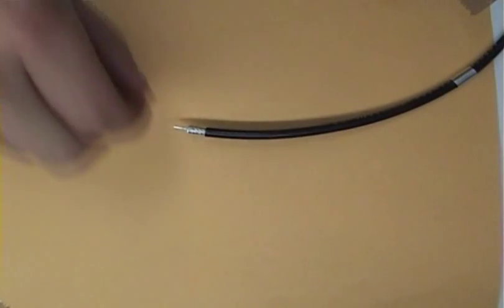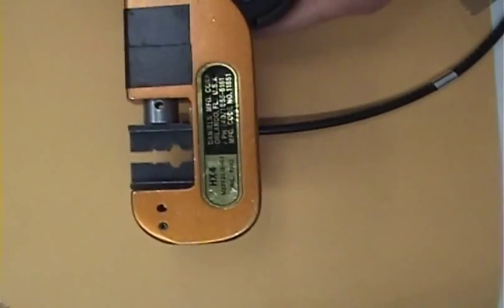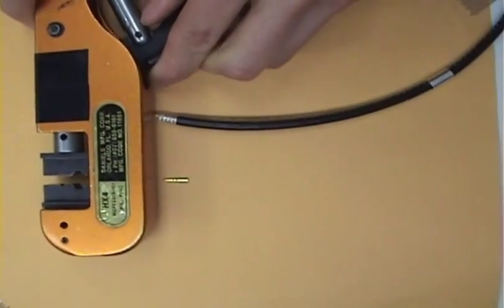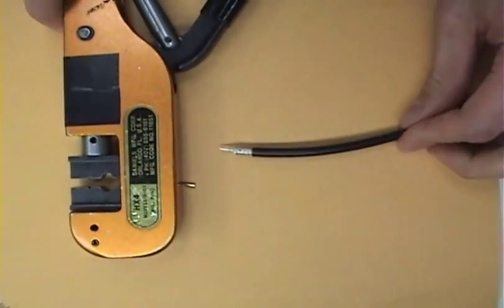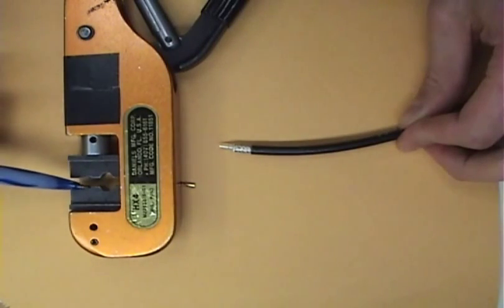I can now prepare to crimp the pin onto the center conductor. To do this, I use the DMC HX4 crimping tool along with the die set Y205P. Use closure B to crimp the pin.